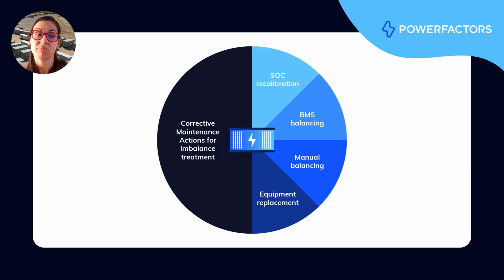The frequency that recalibration may be needed varies depending on application, age of the battery, and operational cycles, but we've seen that it can be as often as once a month in certain cases. Recalibration cycles require taking the system or part of the system offline, which affects availability and potential revenue during that period. Every hour of BESS downtime used to balance or recalibrate the battery is a lost opportunity to deliver energy services through frequency regulation, peak shaving, and so on. This can heavily impact a project's ROI depending on the frequency of maintenance routines, and especially in high-value markets.